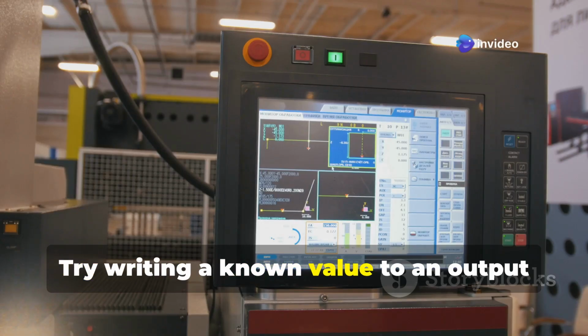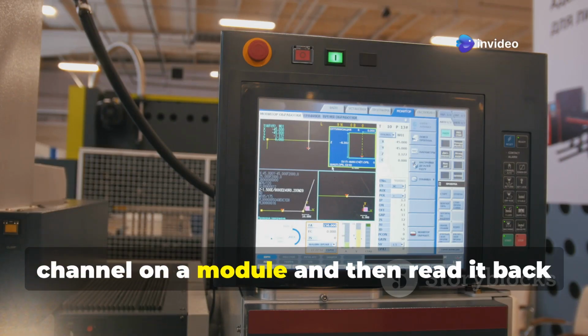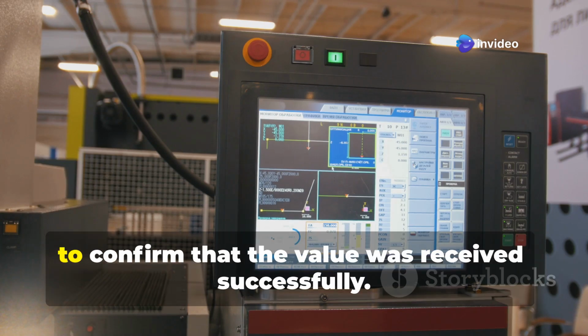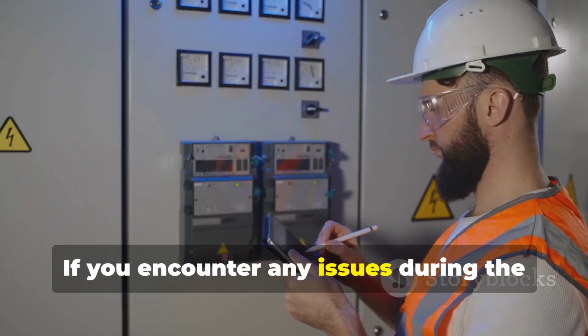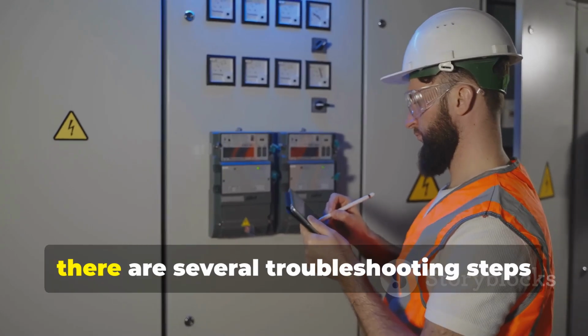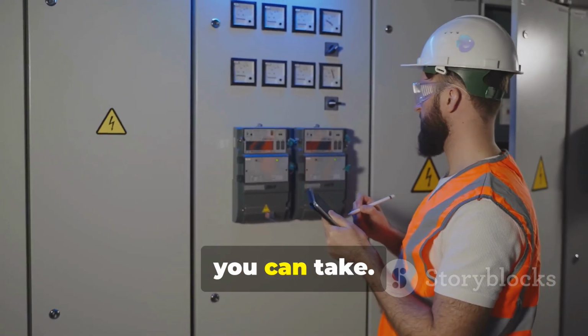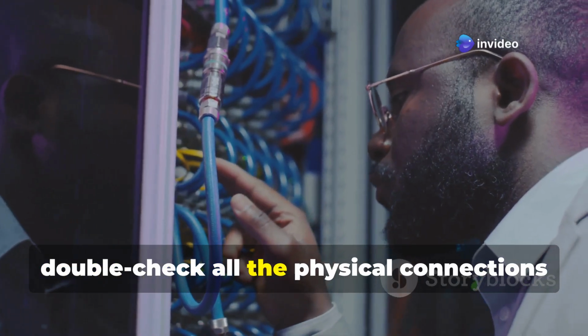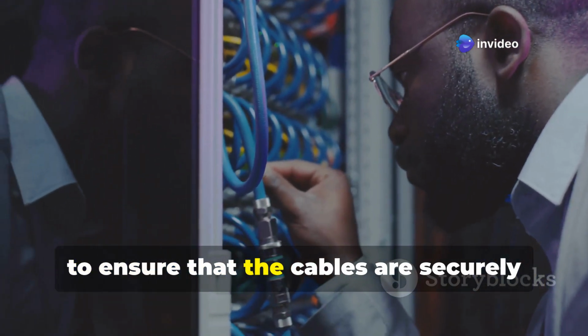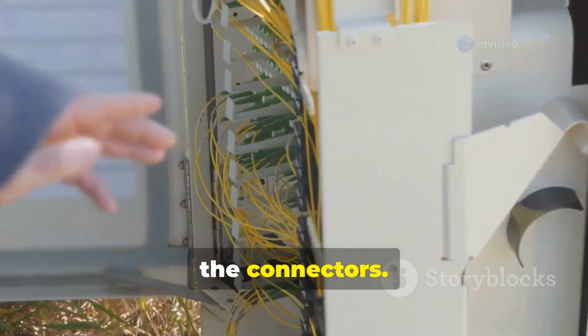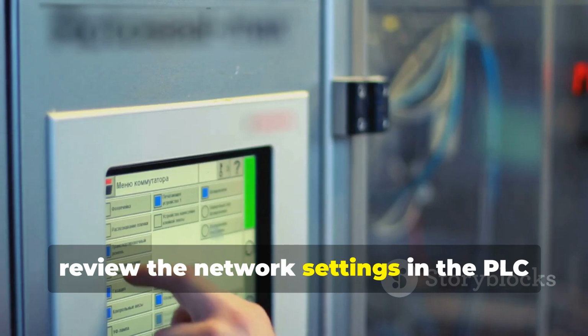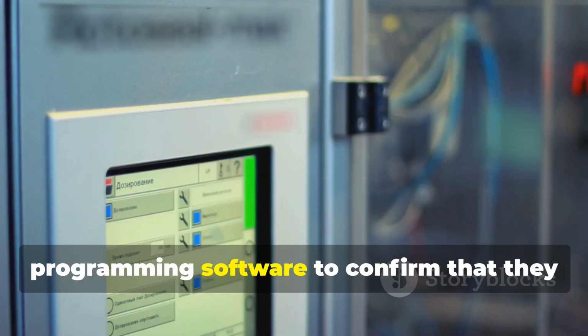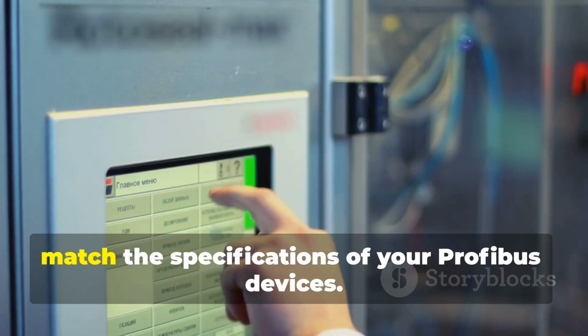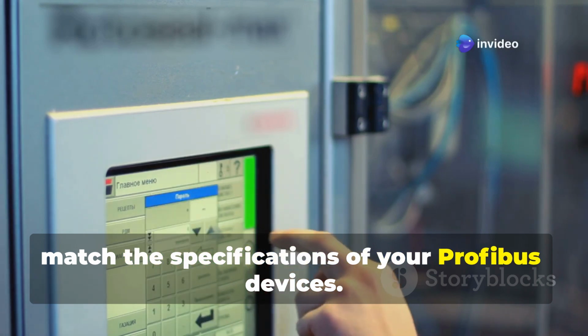Try writing a known value to an output channel on a module and then read it back to confirm that the value was received successfully. If you encounter any issues during the verification process, there are several troubleshooting steps you can take. First, double-check all the physical connections to ensure that the cables are securely plugged in and that there is no damage to the connectors. Next, review the network settings in the PLC programming software to confirm that they match the specifications of your Profibus devices.